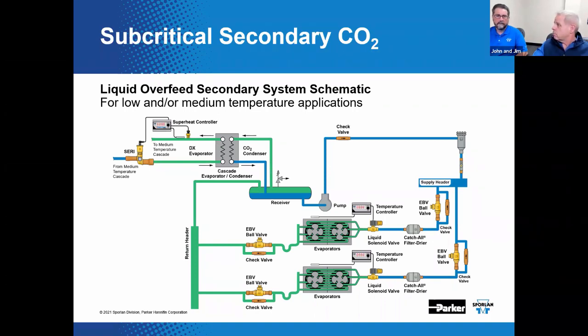Correct. In an air conditioning system, you could almost say that the air being circulated within the building is a secondary refrigerant of sorts. Maybe. In a lot of ways, it really is, yeah. You want to look at it that way. The systems can be used for both low temperature and medium temperature operation. However, only one CO2 liquid pump station can realistically be used per temperature level.